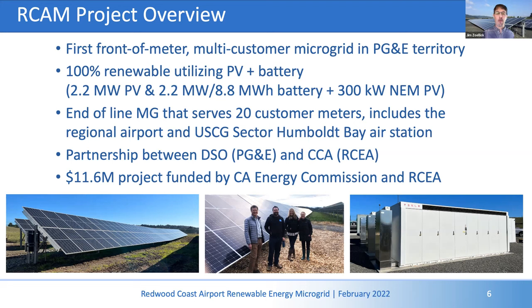Our project is 100% renewable, utilizing PV and battery. The key critical facilities do have backup generators on standard automatic transfer switches, and those now are just deep backup - if we run out of PV and battery power in a long outage, those backup generators could be called into service. It's 2.2 megawatts of PV, DC coupled to a 2.2 megawatt, 4-hour, 8.8 megawatt hour battery.